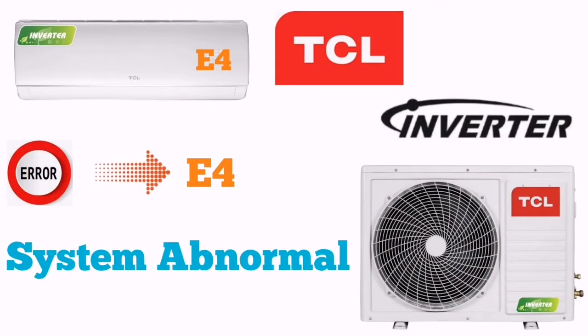When you see error E4, it means system abnormal in our indoor and outdoor refrigerant cycle. First of all, we have to check the high pressure and low pressure valve. If it's not open, open again to ensure the system circulation is smooth. Even if it is open, or our discharge and suction line are open, then check the system refrigerant.